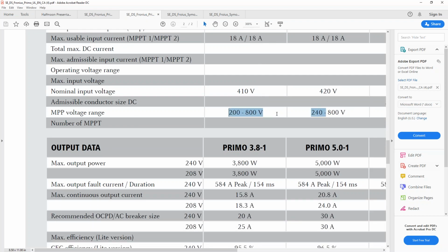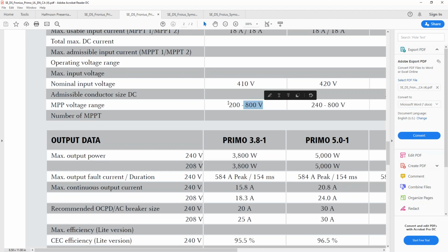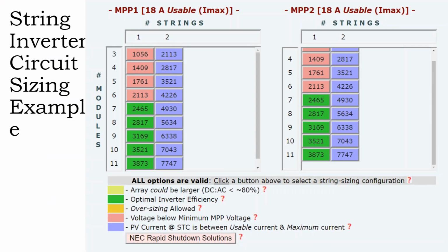What we're seeing here is it says, hey, there's a voltage range for these things where we have to have a minimum voltage of 200 volts and a maximum voltage. In this case, it's made for Europe and it's 800 volts because they have a 1,000 volt maximum. In the United States, we have a 600 volt maximum. And that means we can have fewer modules on a circuit, and that means our systems have more circuits, and that means they're a little bit more expensive. So there is a maximum voltage range and a minimum voltage range, and the string sizing software makes sure that we're staying within that range to not undersize our array and also not make an error by oversizing the array.